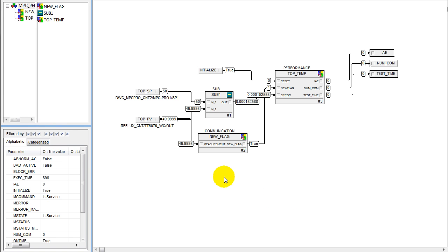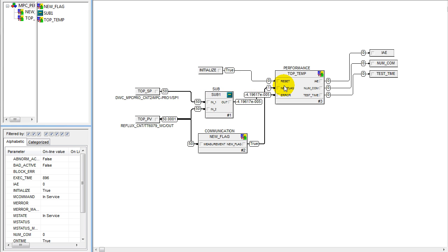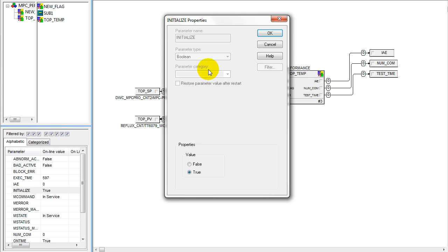By enabling and disabling this parameter, we're able to turn on and off wireless measurements. This is showing the module that we're using to measure performance of the column. We're looking at the difference between the setpoint and actual temperature, then integrating the absolute value of that error to get our integral of absolute error. We're detecting new communications by looking at a change in value, and our calculation sums up the number of new communications.